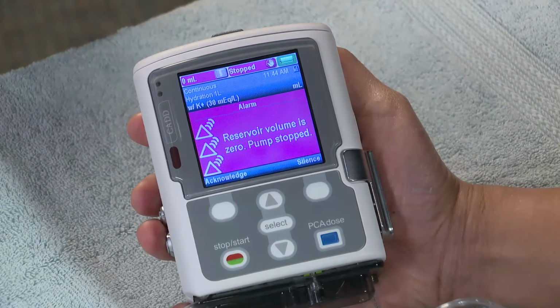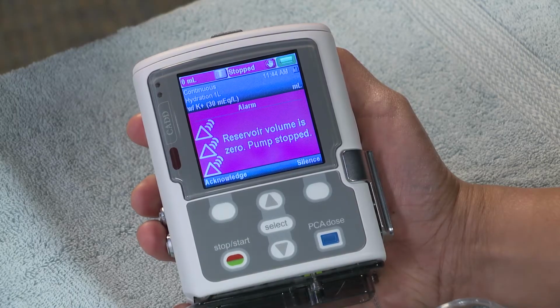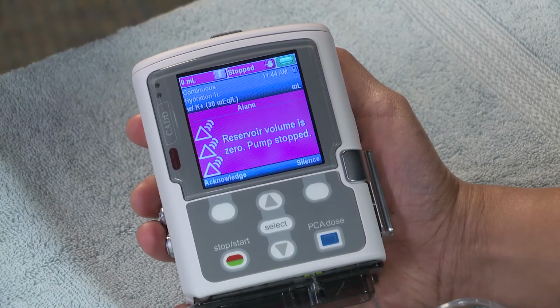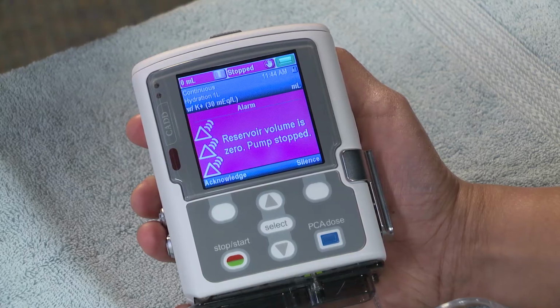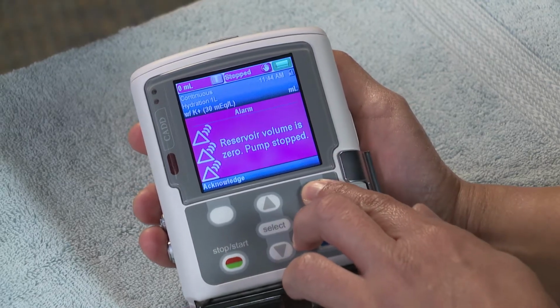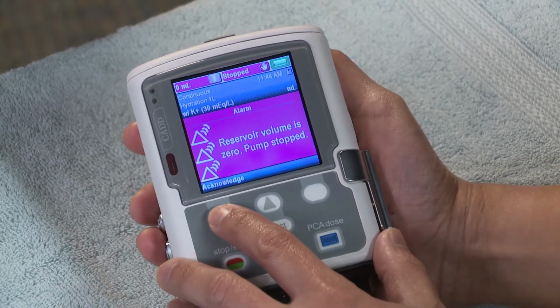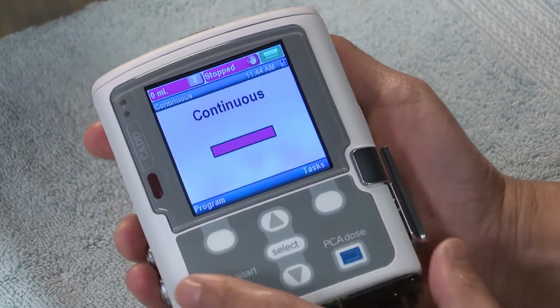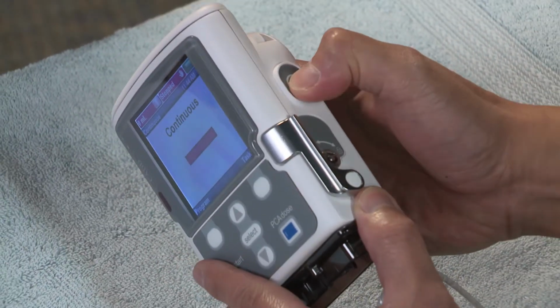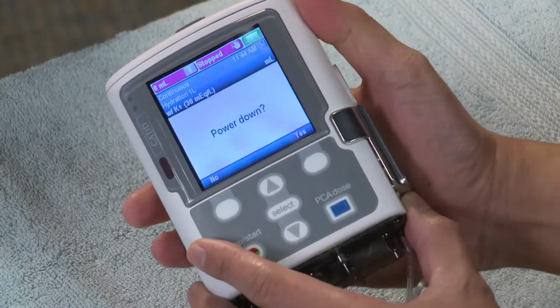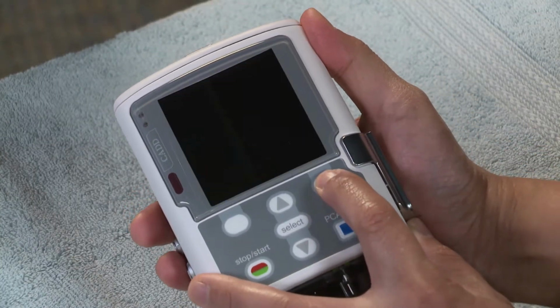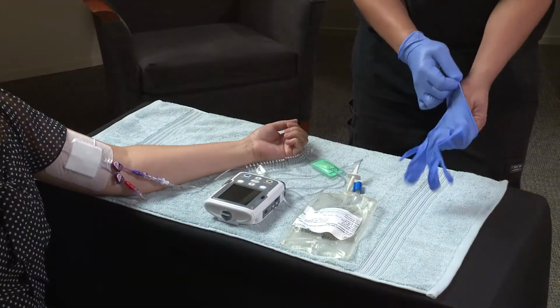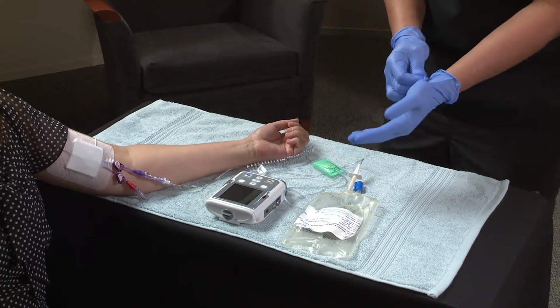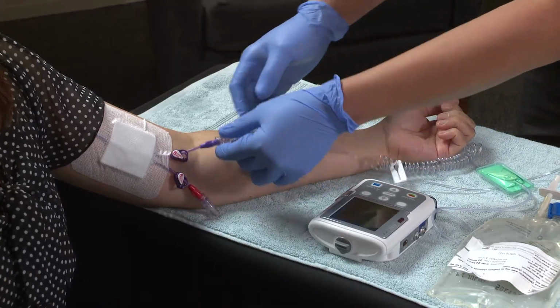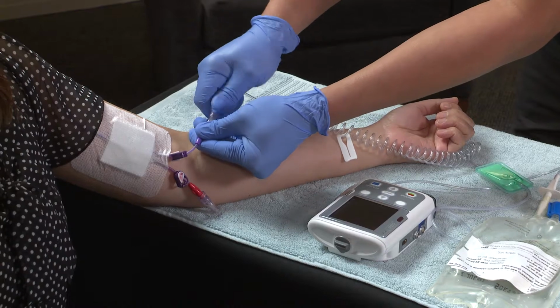When the infusion bag is empty, you will hear beeps and the pump screen will show Reservoir Volume 0, Pump Stopped. Press Silence to silence the alarm and press Acknowledge to clear the alarm message. Leave the batteries in. Put on a pair of clean gloves and disconnect the IV tubing from the IV catheter.